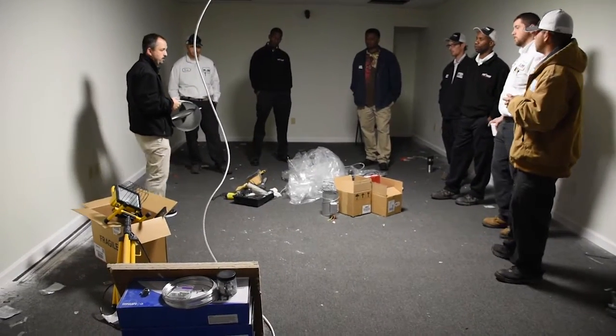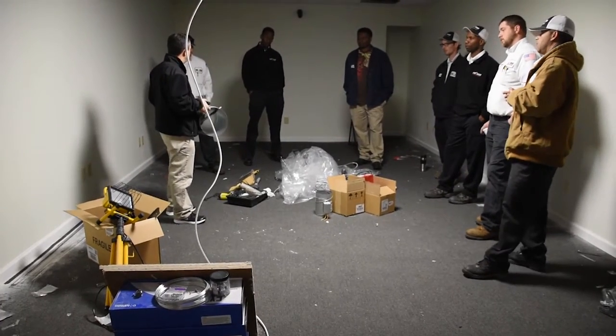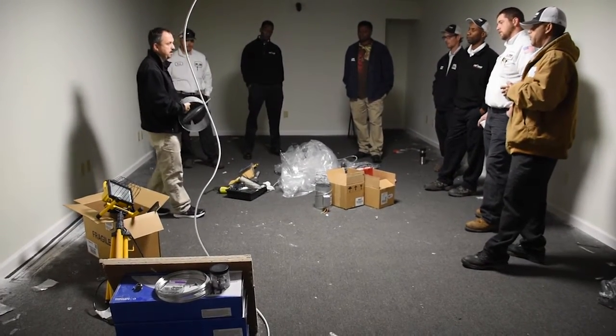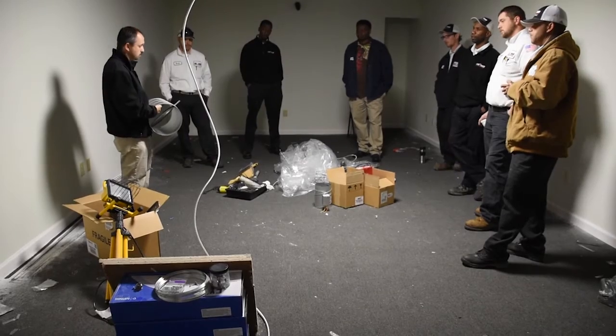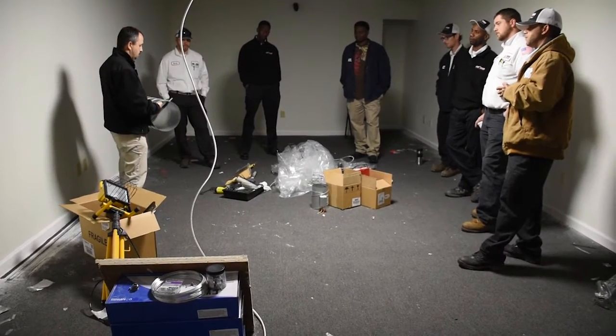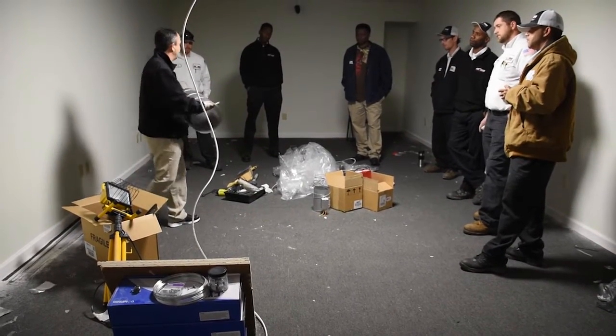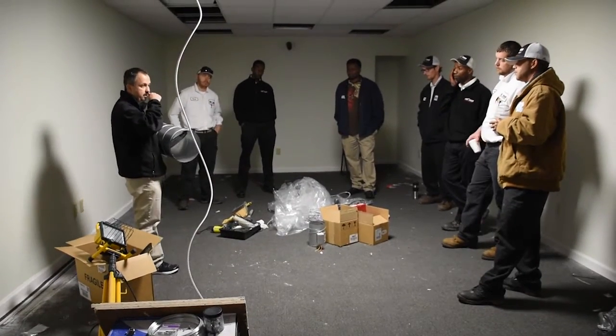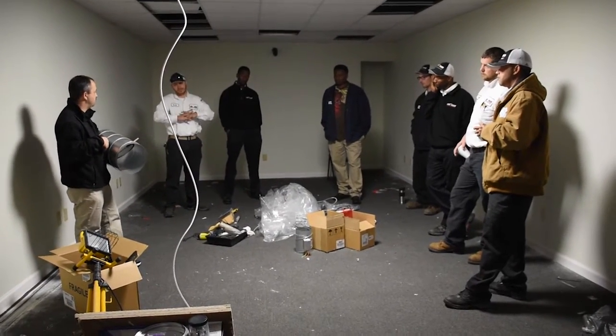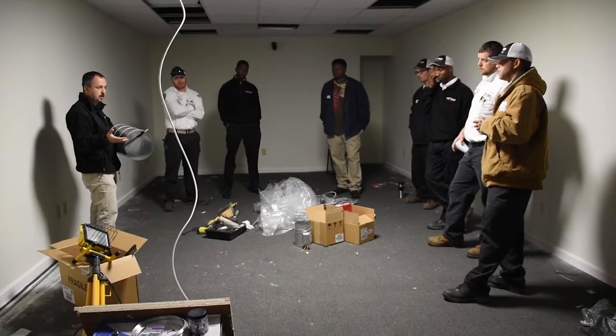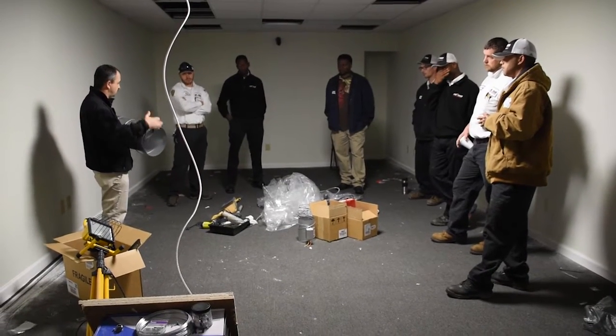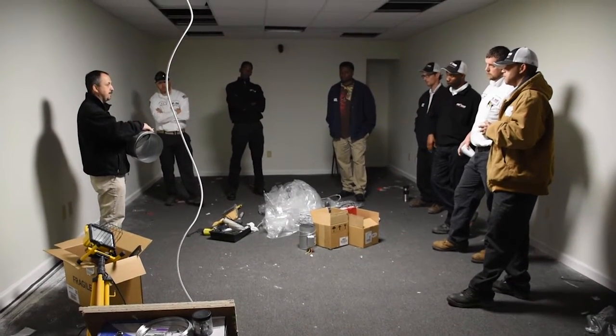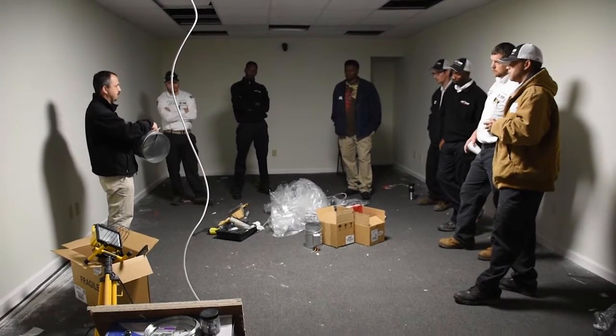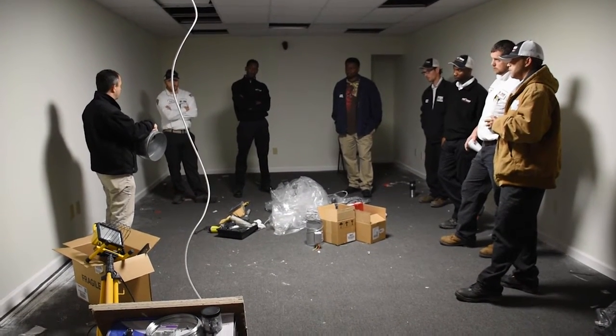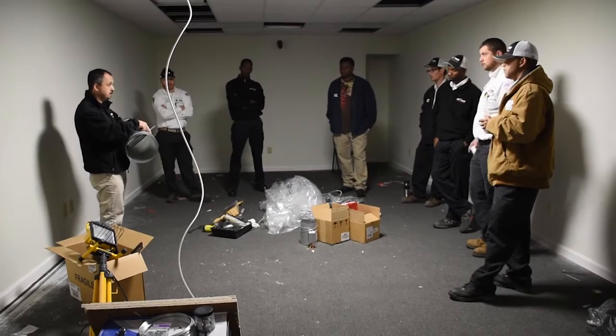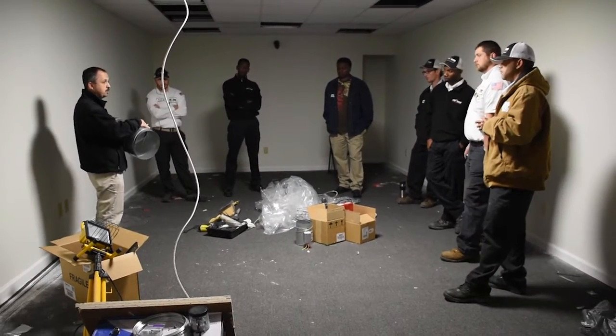Airflow area—which way does that airflow need to go when you install it? This is the bypass, which way does that airflow need to go? Toward the return, that's right. Anytime you go to a job and you're troubleshooting, trying to figure out what's going on—pressures are crazy, it's not cooling like it needs to, you don't have good airflow—go to the bypass damper of the zone system and verify that the arrow is pointing the right way. You might have to cut the insulation on it to see it. Just make sure that it's pointing the right way.